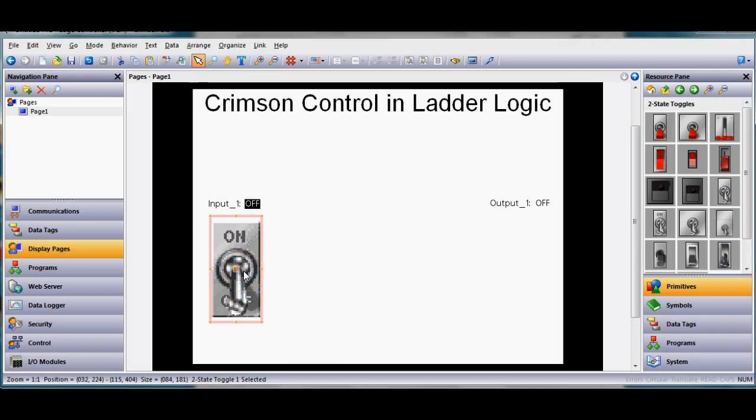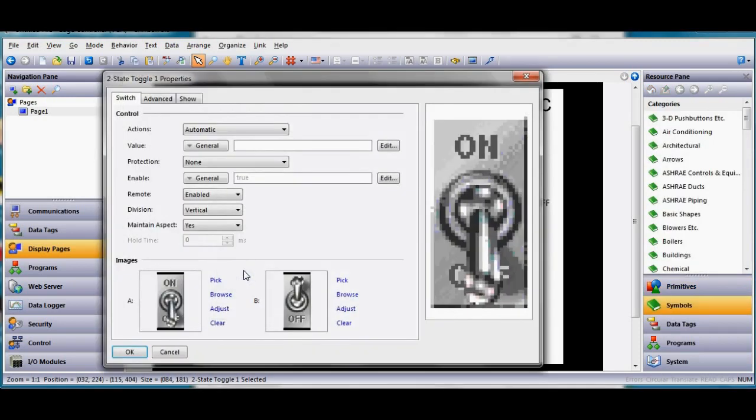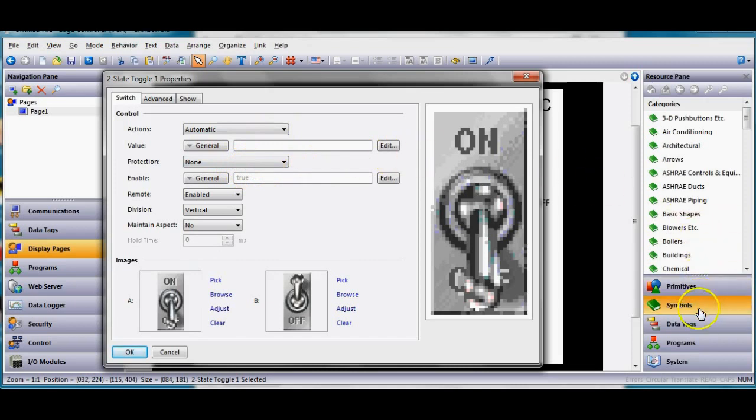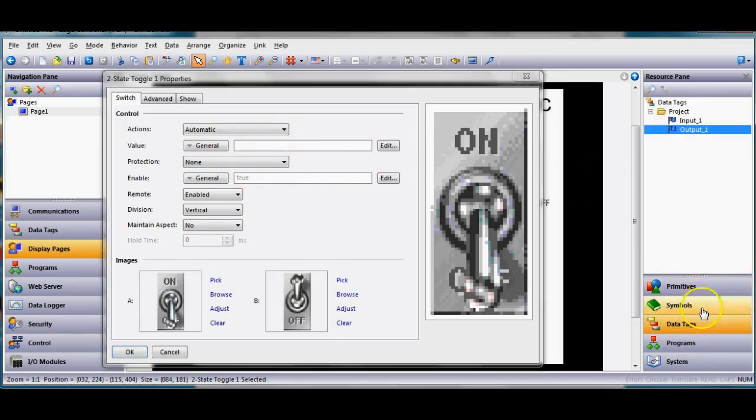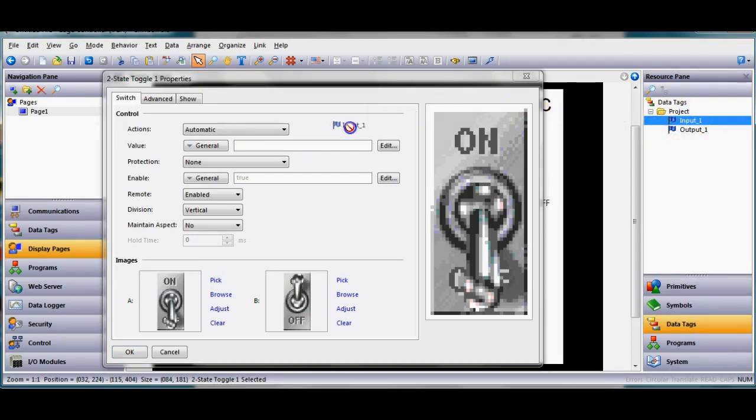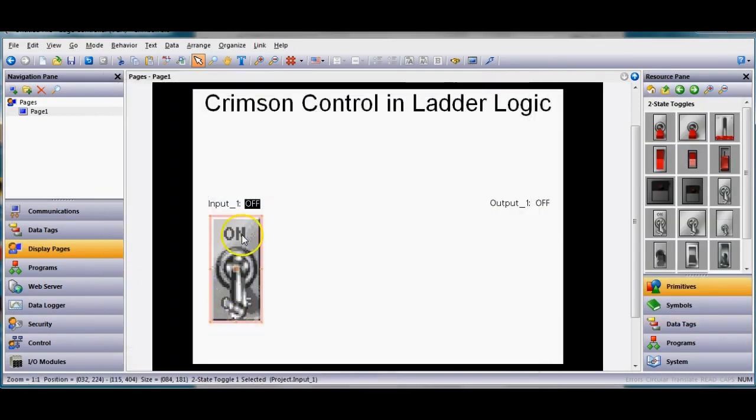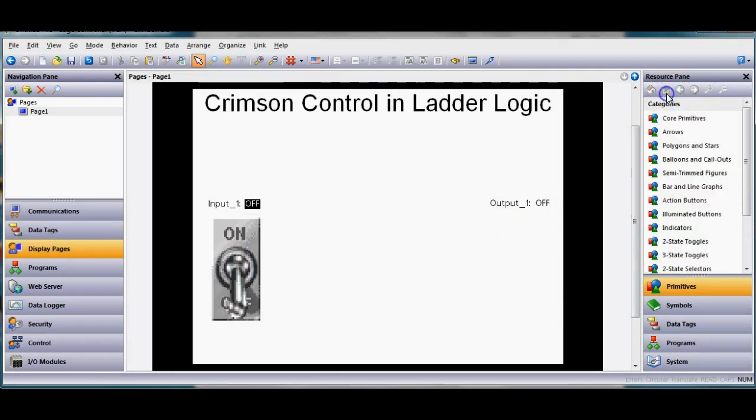I'm gonna link this graphic to my input one by doing a simple double click and I want to make this guy control my input one. So I'm gonna go over to the right side go to data tags on the right side and I'm gonna grab input one and drag that tag right here in the value field, boom. Now I should really control that with this here.